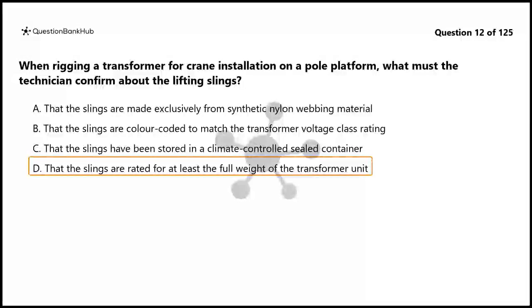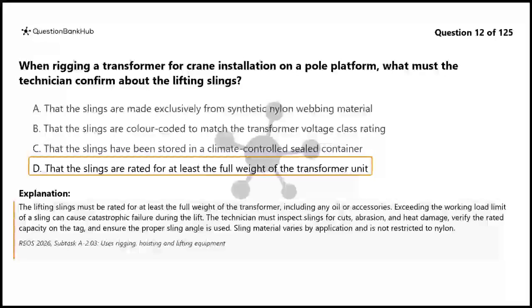The correct answer is D. The lifting slings must be rated for at least the full weight of the transformer, including any oil or accessories. Exceeding the working load limit of a sling can cause catastrophic failure during the lift. The technician must inspect slings for cuts, abrasion, and heat damage, verify the rated capacity on the tag, and ensure the proper sling angle is used. Sling material varies by application and is not restricted to nylon.